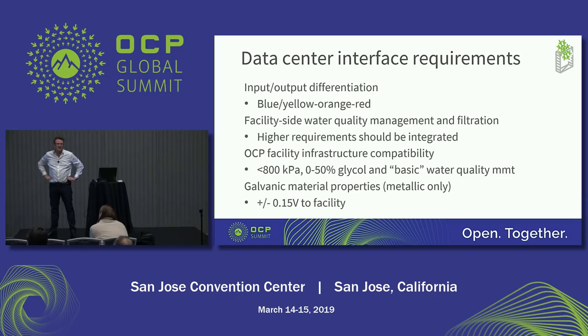On the glycol, one of the things that liquid cooling uses is you have to add, I think it's necessary to add the pH level on the glycol because it's like 7 to 9. For the glycol, you have to run it basic. As soon as it gets acidic, you have to flush it. All right, please do mention that in the workstream call so we can give it a place. That's great input, thanks.